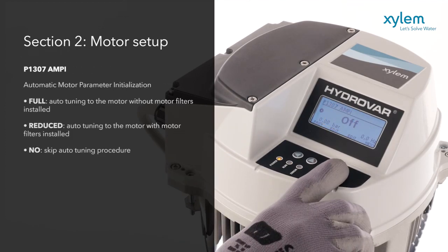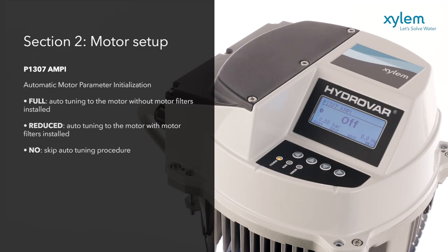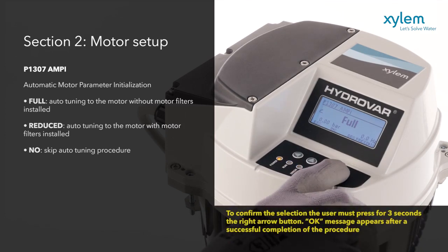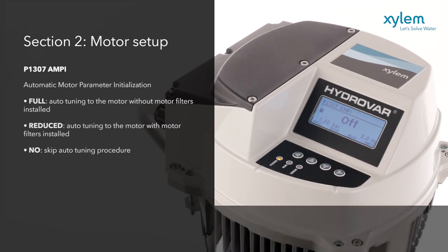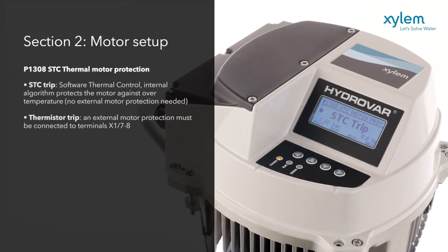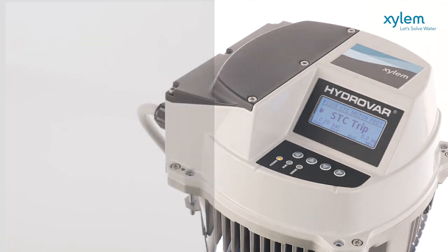Note that the Automatic Motor Parameter Identification process, AMPI, can take up to 3 minutes, during which time no other actions are possible. It's necessary to select the thermal protection settings for your motor, which will protect the unit from overheating. With the STC, Software Thermal Control, no motor PTCs are required as standard.